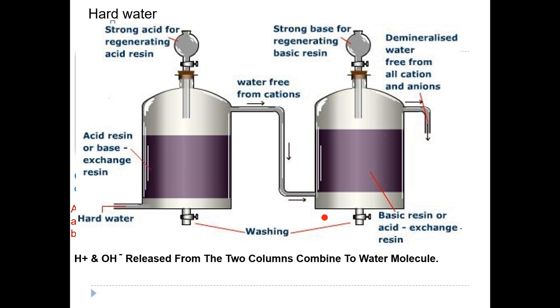Eventually the resin gets exhausted — all the H+ ions are replaced by cations, and all the OH– ions from the resin are replaced by anions. The step to restore the resin is called regeneration. For the cation exchanger, regeneration is done by passing an acid solution like HCl — the H+ ions replace all the other cations. For the anion exchanger, a strong basic solution is added so that OH– ions replace all the anions.